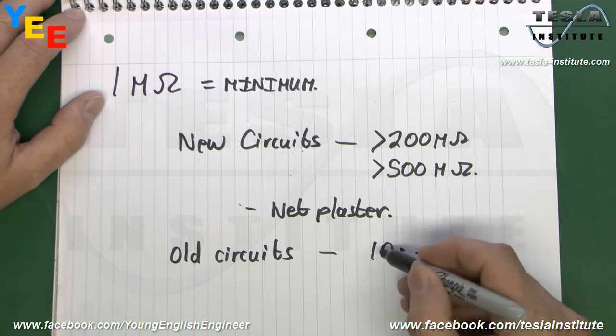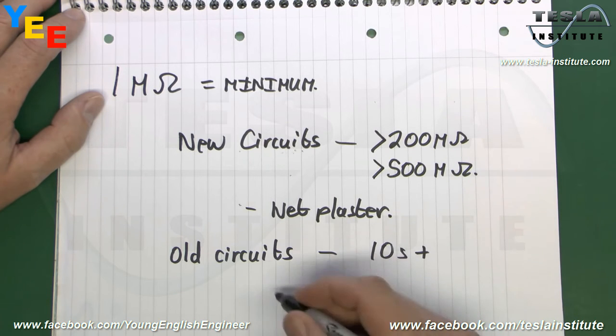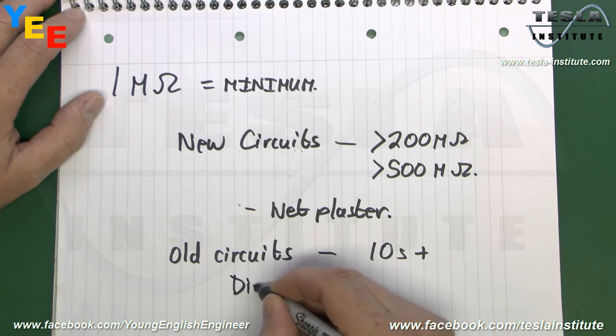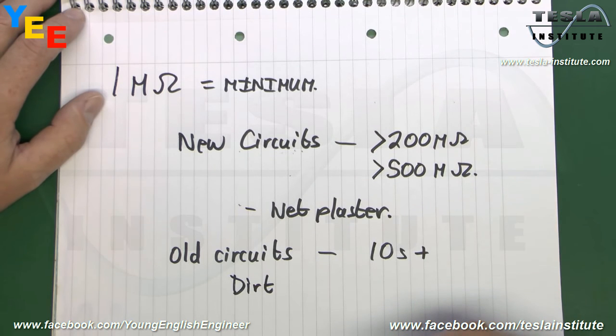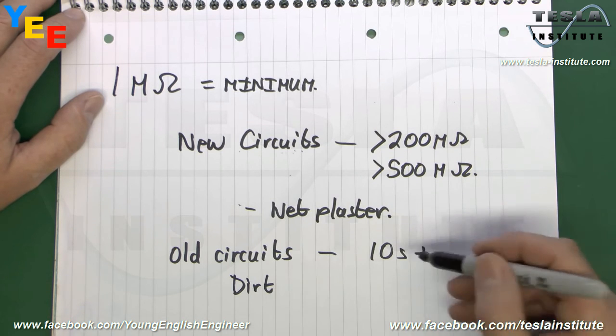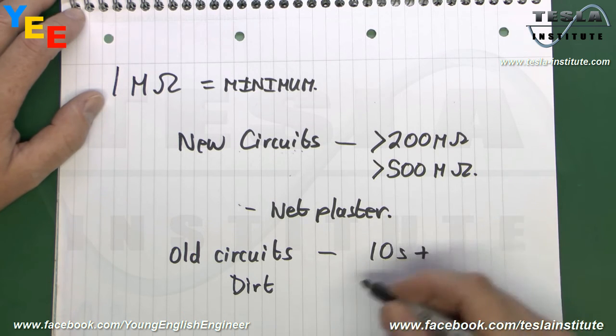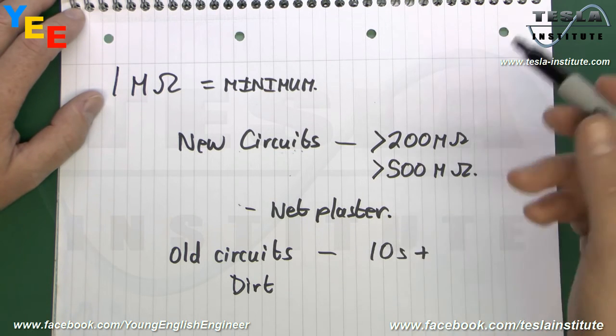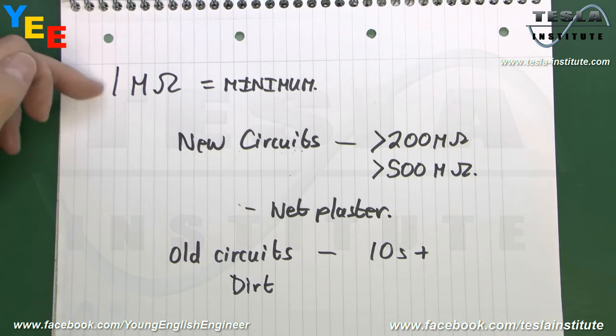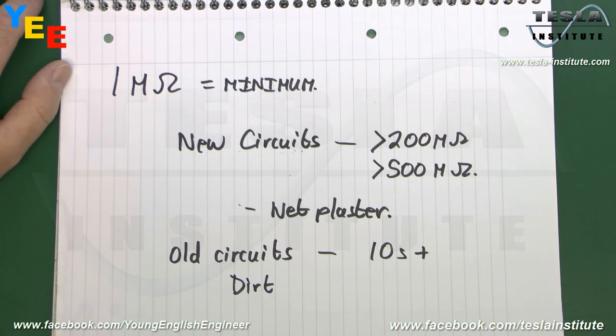In these cases, the problem is usually due to things like dirt over the wires in the back of the socket, where it's got covered in filth and mess. It's fairly uncommon to find that a damaged cable will give results in this kind of area. Typically, if the cable's damaged, you're going to be looking at values far less than 1, which is primarily why the 1 was chosen.